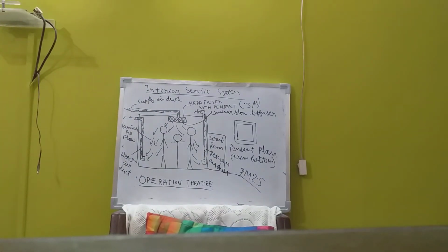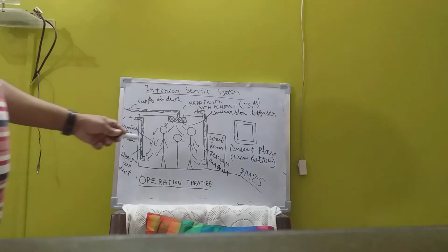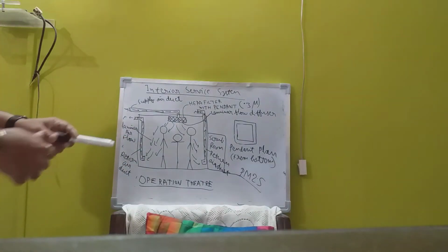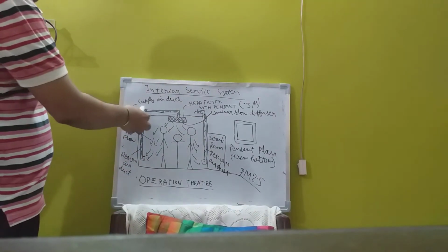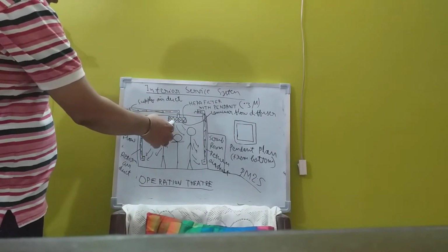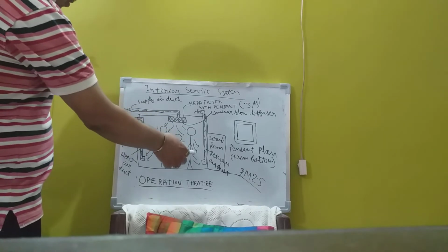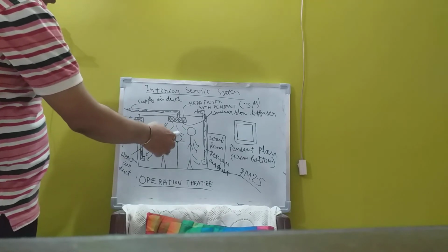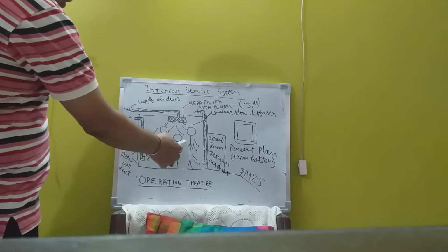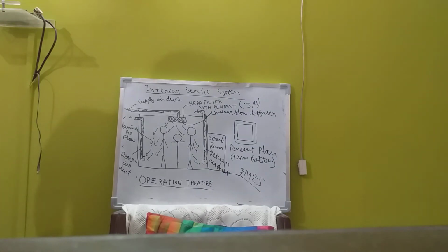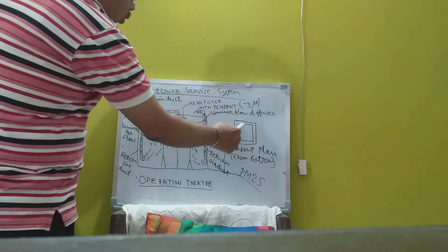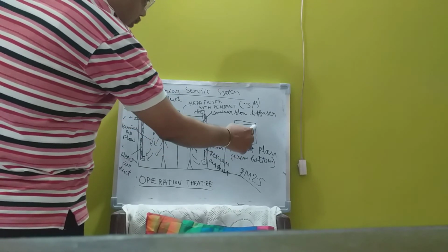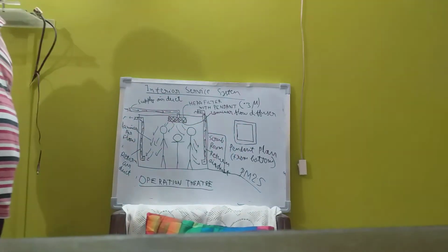This is very important to understand, the working of the operation theatre, how the scrub room works. Again, I am telling, the AHU supplies air through the HEPA filter and laminar flow diffuser in a laminar flow pattern within the room. These are the doctors and nurses, this is the patient, with the doctors and nurses surrounding the operation table. From above, the HEPA filter arrangement will look like this. In between there will be the HEPA filter. Outside there will be the lighting. This is called the pendant.